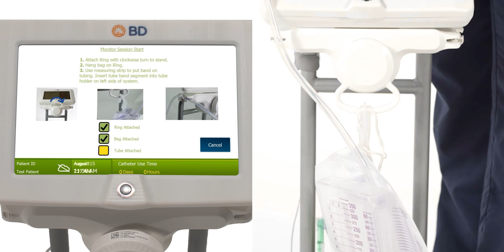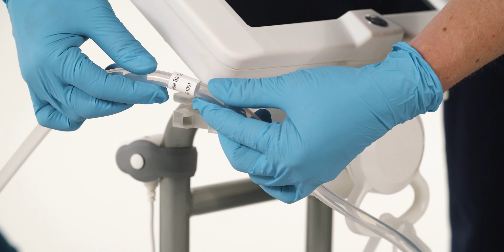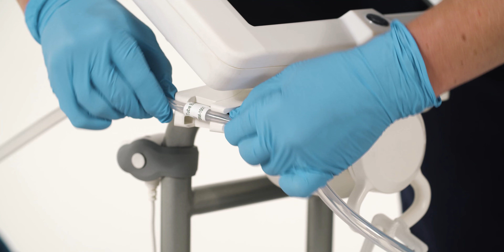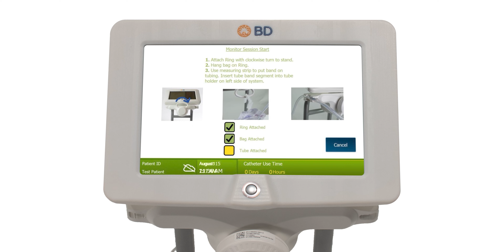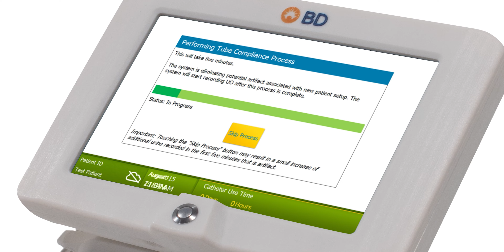Next, hang the bag on the ring. Now the tubing can be inserted. Squeeze the edge of the tubing and put it into the holder so the tube bands line up with the tube holder window. After attaching the bag and tubing, the Sensica urine output system will automatically start a one-time tube compliance process, which takes about 5 minutes. If immediate monitoring is needed, you can touch Skip Process and the monitoring session will begin.